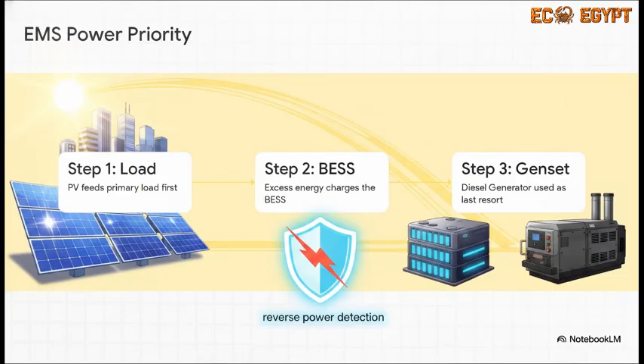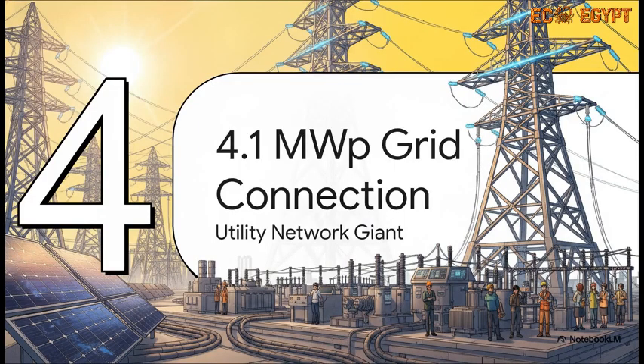And here's exactly how they manage it, through a very strict Energy Management System, or EMS. Step 1 is straightforward. The PV array always feeds the primary load first because it's your cheapest energy. Step 2, any excess solar energy is immediately routed over to charge up those BESS units. Step 3. The diesel generator is strictly a last resort. It's designed to start automatically only when your solar drops and the batteries are completely depleted. They even use reverse power detection to ensure solar power never accidentally backfeeds into the diesel generator, because that would literally destroy it.